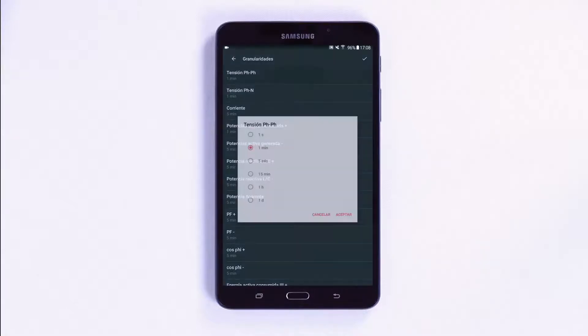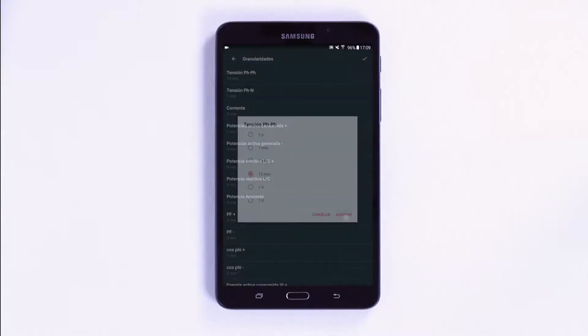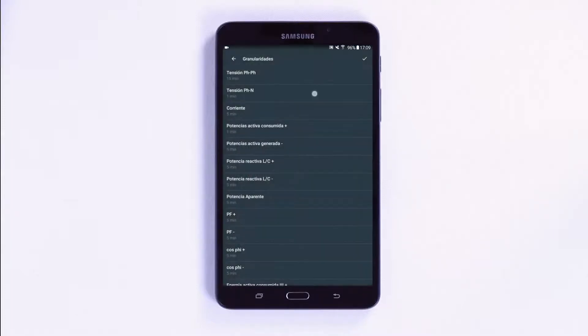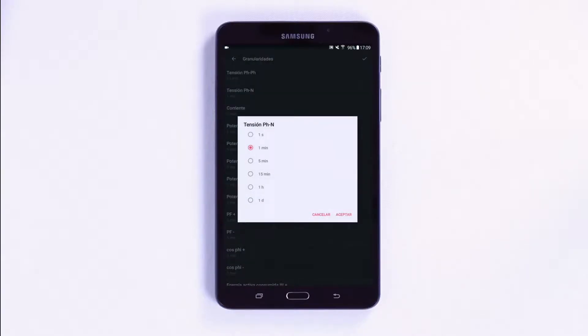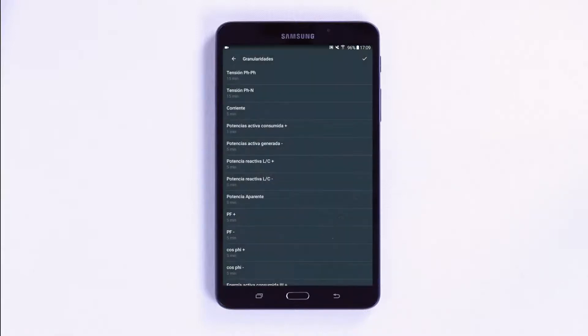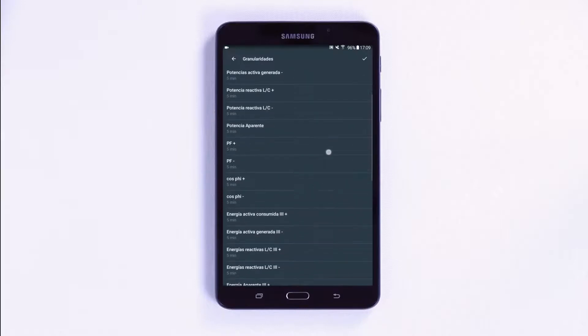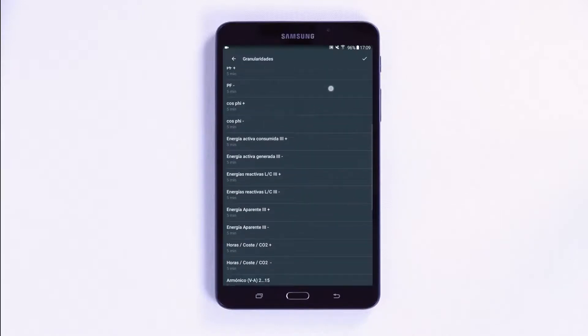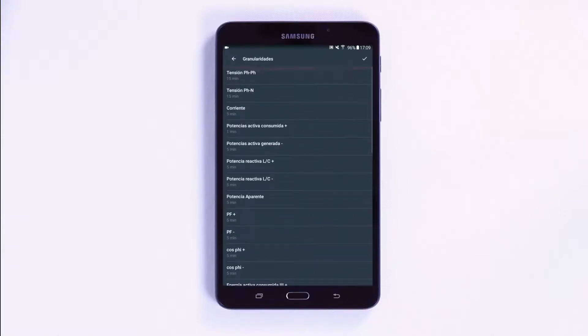If you enter the Granularities menu, you can configure the recording period for each variable individually. In this way, each variable can be recorded and integrated at a 1 second, 1, 5 or 15 minute, 1 hour or 1 day interval. For a more detailed study, it is possible to select different variables at 1 second intervals, such as voltage and current, and others every 15 minutes, such as power or energy, like an official billing meter does.